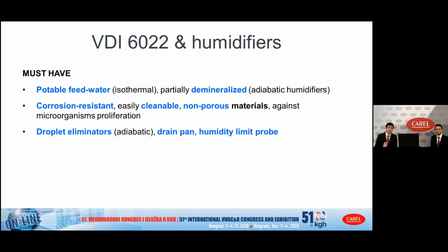Using adiabatic humidifiers, there is a strong suggestion to use droplet eliminators, avoiding letting water end up on equipment inside the handling units. We must stop the water in the humidification chamber and drain it to the pan, taking it away in order to spray only clean water and not let the water stagnate, which can cause proliferation of bacteria. All of you know the Legionella bacteria, which is really dangerous for health and causes something similar to pneumonia—like COVID, but a different bacteria and virus.